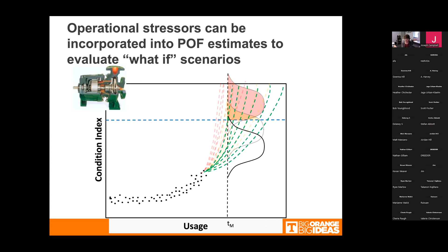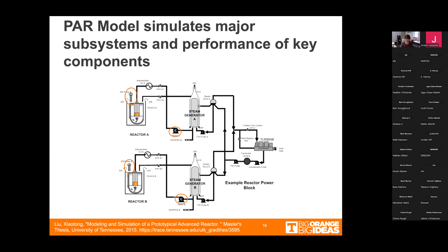We then looked at the same prototypical advanced reactor power module setup and developed a simulation model, primarily built by a master's student at UT, Xiaotong Liu, modeling the primary system of the reactor, the steam generator, and the balance of plant. It also models degradation of, in this case, just the reactor coolant pump and the intermediate pumps. You could also look at valves, heat exchangers, and the steam generator, but as an initial step we started with these two pumps.